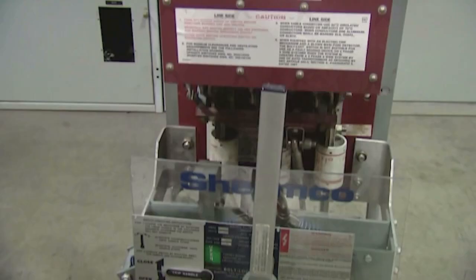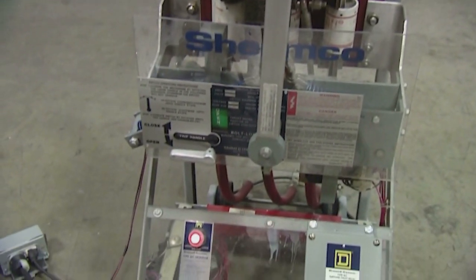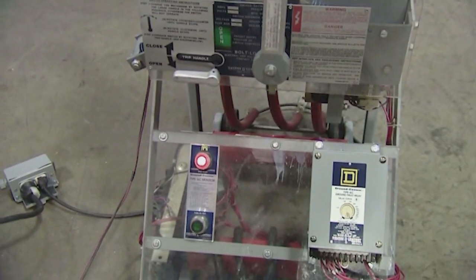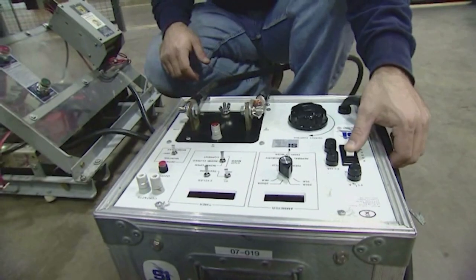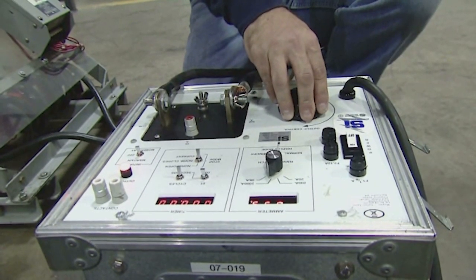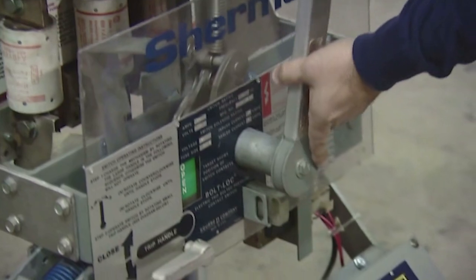I've said several times that we're going to do this by primary current injection, and oftentimes I hear, well, it's not possible to do primary current injection at an installation, and that's actually not true. We were involved quite a bit in getting the language of the National Electric Code to say by primary current injection because it's a simple test to do in the field. We've got many years of experience doing this, and all you need is a 110 volt source, an amp bucket, a current supply, and then you can run conductors through the CTs, do current injection at the primary current fault level, and then trip the relays.